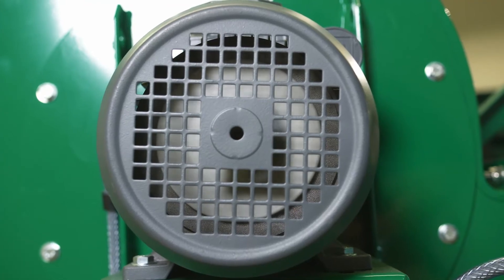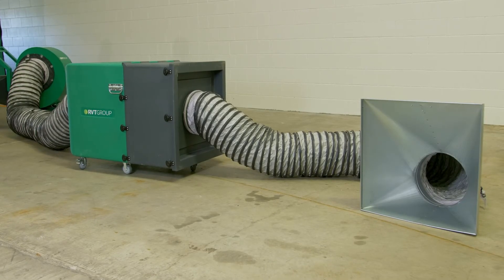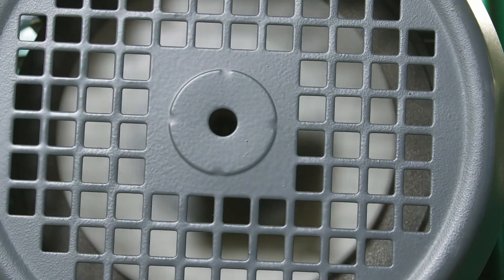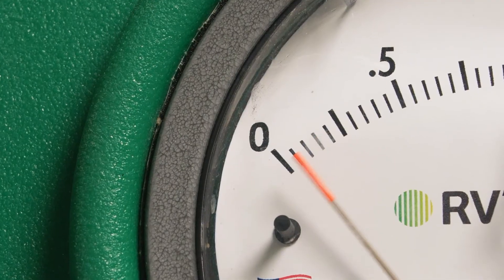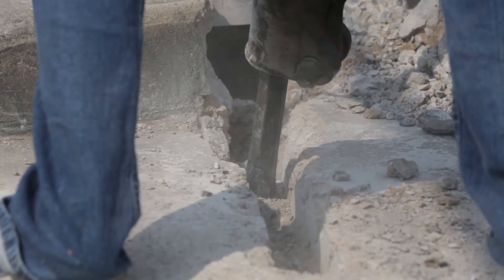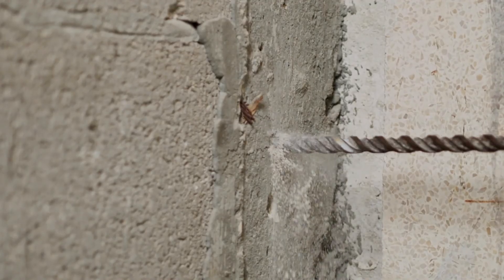The Wanda Filter is normally coupled with an extraction fan, ducting, and a capture hood. Along with filtration, air changes are a critical part of creating a safe working environment. The Public Health Authority in the UK published findings that a single air change is estimated to remove 63% of airborne contaminants, and after five air changes, less than 1% of the original airborne contamination is thought to remain.